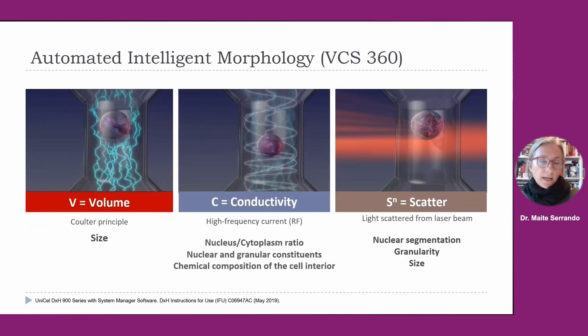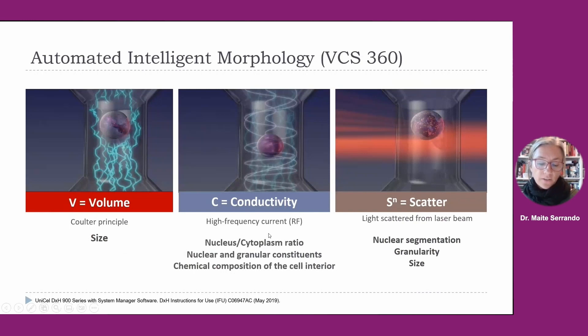In this slide, we can see how the automated intelligent morphology module works. With this module, we can obtain differential leukocyte information using three measurements that measure individual cell volume, high-frequency conductivity, and laser light scatter. The combination of low-frequency current, high-frequency current, and light scattering technology provides the system with abundant cell-by-cell information, translated into data plots. Here we can see the relation between volume and cell size via the Coulter principle, conductivity related to nucleus and cytoplasm ratio, nuclear and granular constituents, chemical composition of the cell interior, and laser scatter information related to nuclear segmentation, granularity, and cell size.